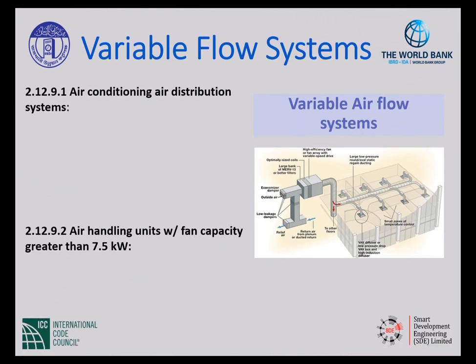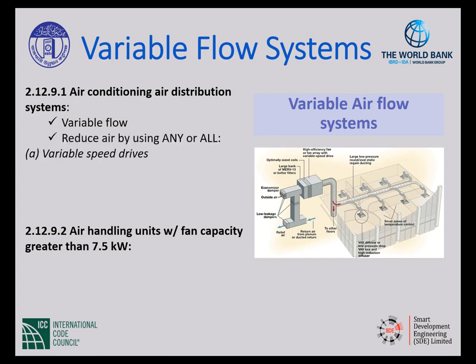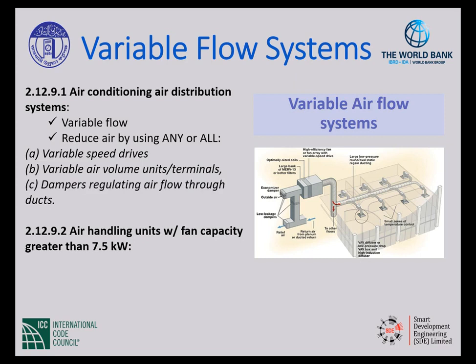And then when we get in here, we talk about these variable flow systems some more. So air conditioning and air distribution systems have to be designed for variable airflow, right? So they have to be capable of reducing the airflow, and you can do it in a couple different ways, either by variable speed drive or variable air volume units, a VAV system, or dampers regulating the airflow through the ducts. So I see a lot of times either a variable speed drive or VAV units to address this, but you have to choose one of those.